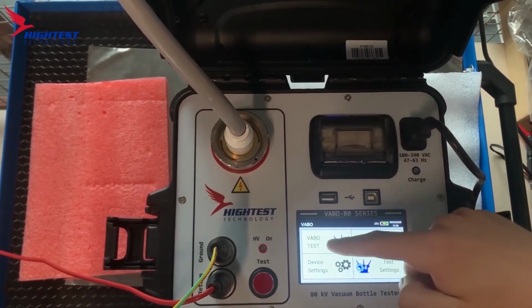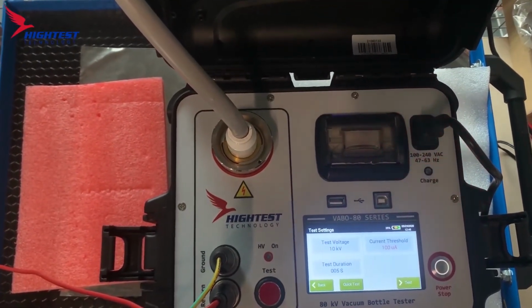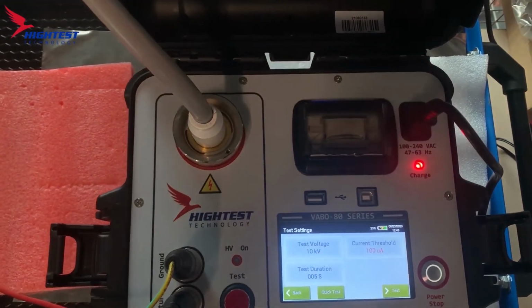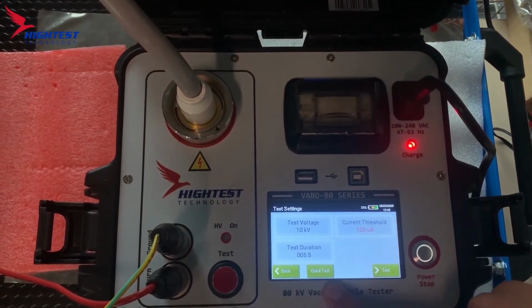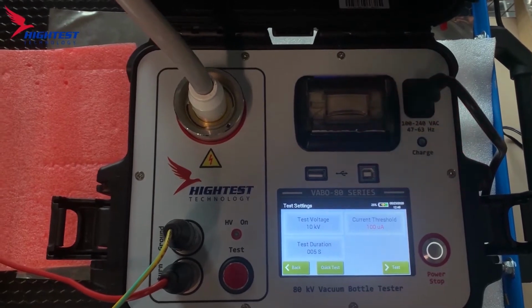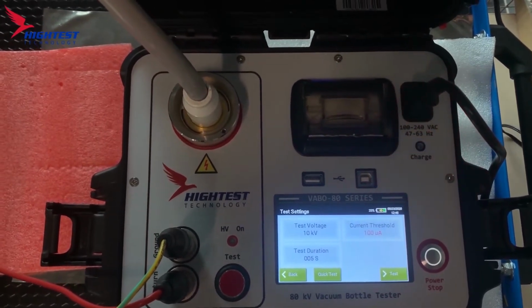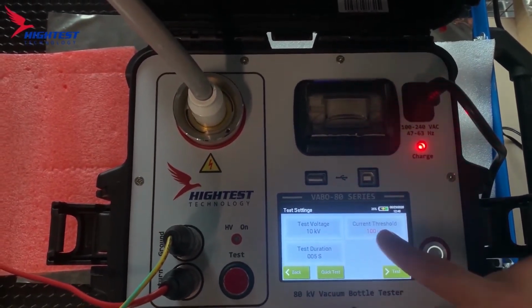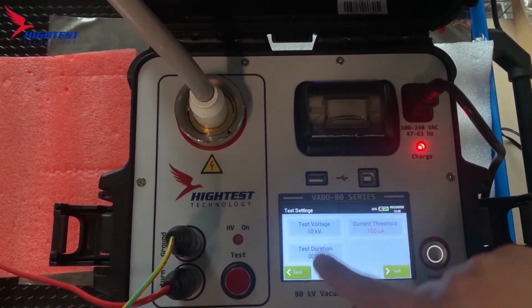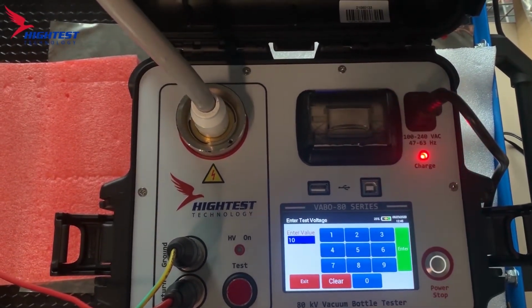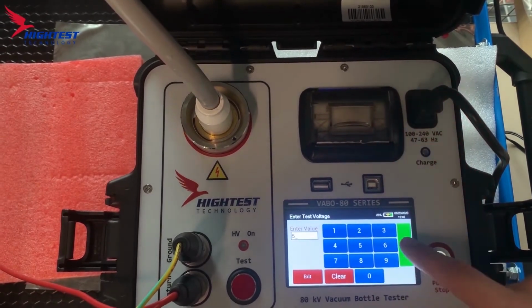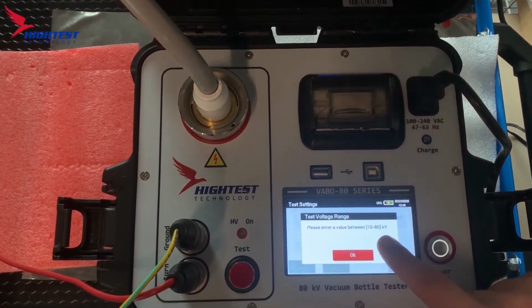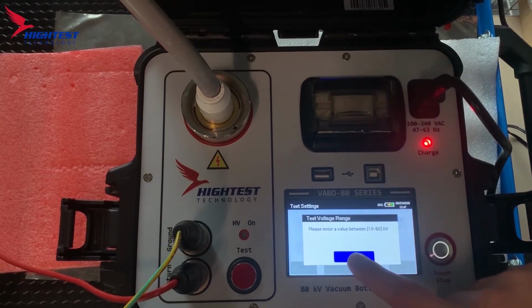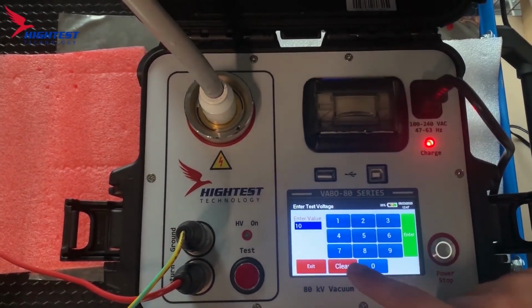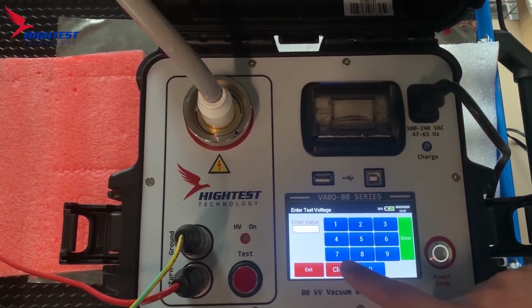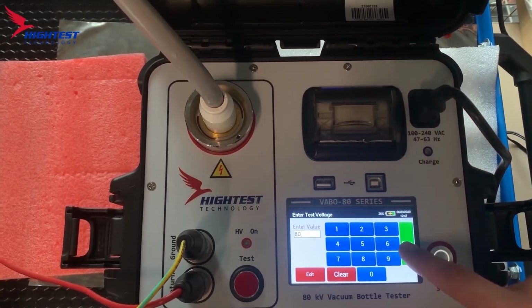As you can see here, please click VABO test to enter in the test information. Here you can perform a quick test from settings given in the test settings in the main menu, but we will not be focusing on that. Instead, we will be focusing on the main settings. Here for test voltage, you can select test voltages between 10 and 80 kilovolts. For this test, we will be conducting it at 80 kilovolts.